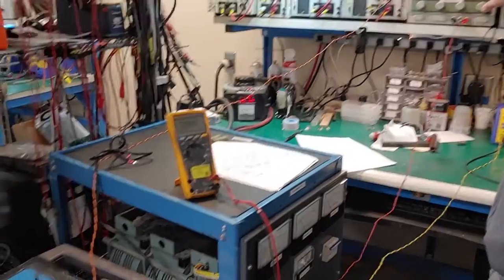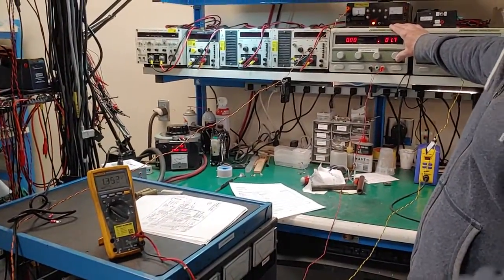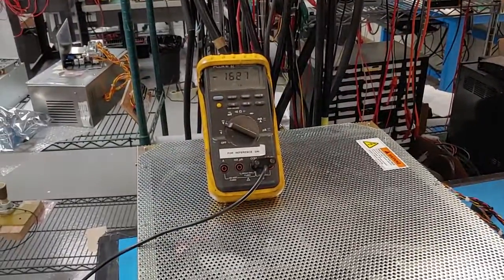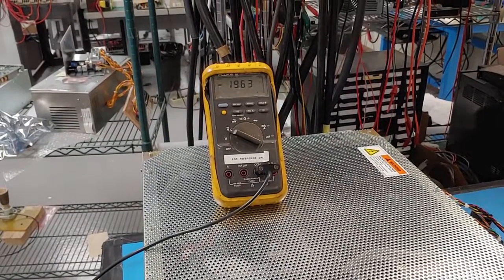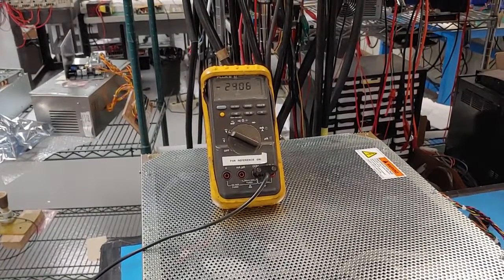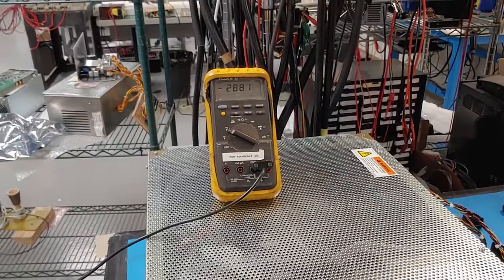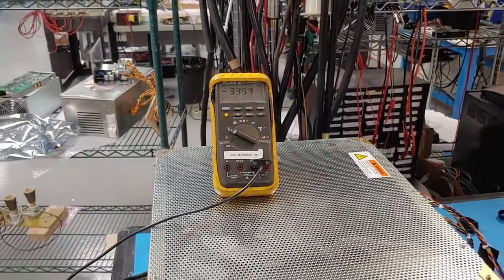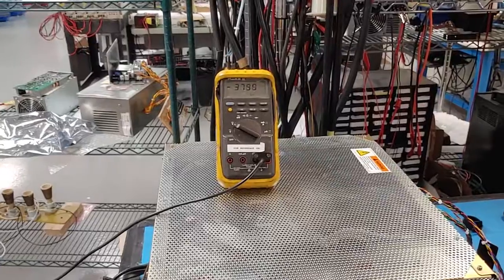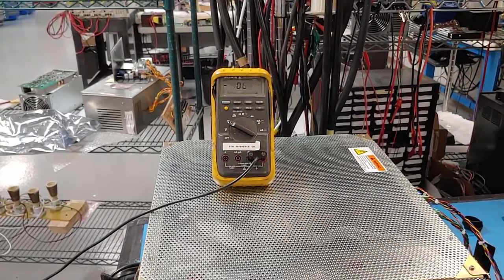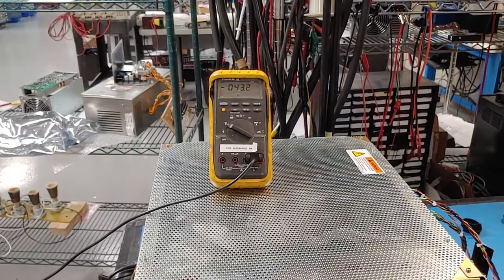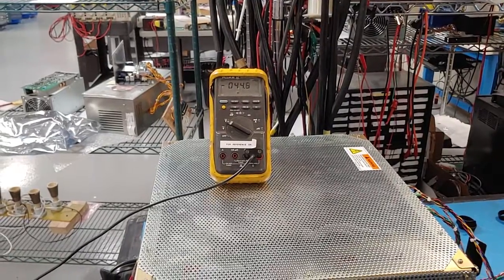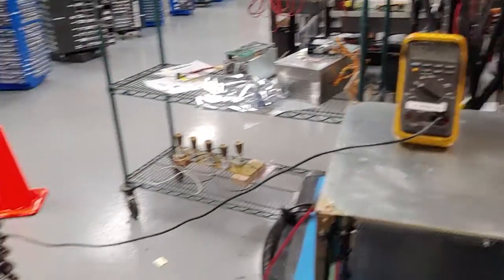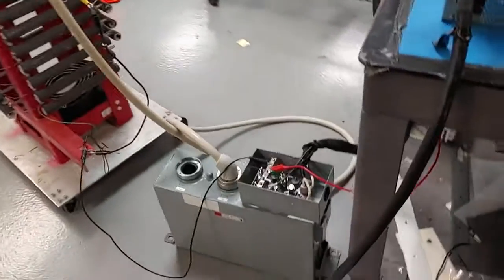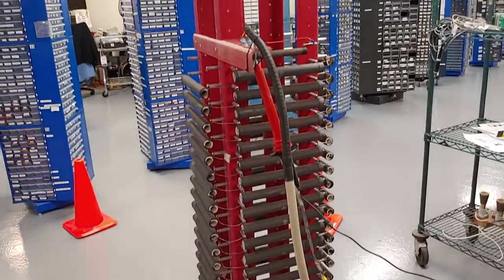Slowly increase this. We're not going to do it real hard. So there's 10,000, we're going to go to 15, it's 20,000 volts. I'm going to take it all the way up to 60. I'm going to go slowly. I don't want to overshoot it on this one. It's currently being loaded through 1.5 million ohm resistors. That's most of the resistors on the bottom side of that stack. About 68 of them to be exact. All right, we're coming up to 50,000.